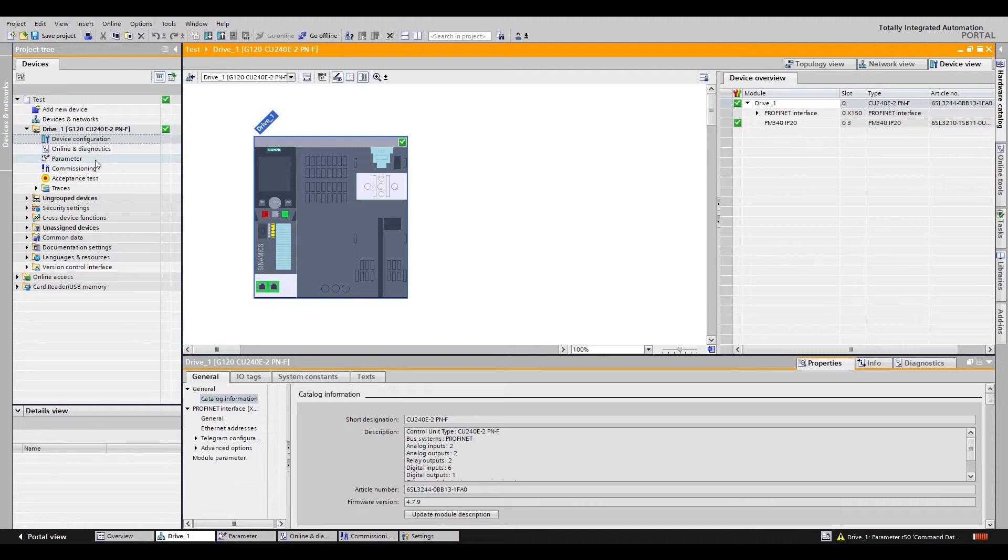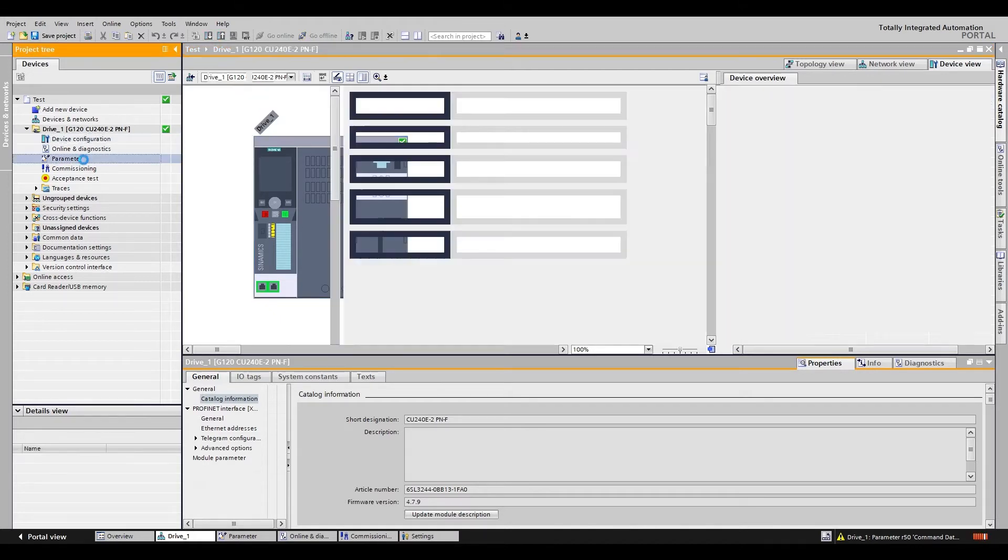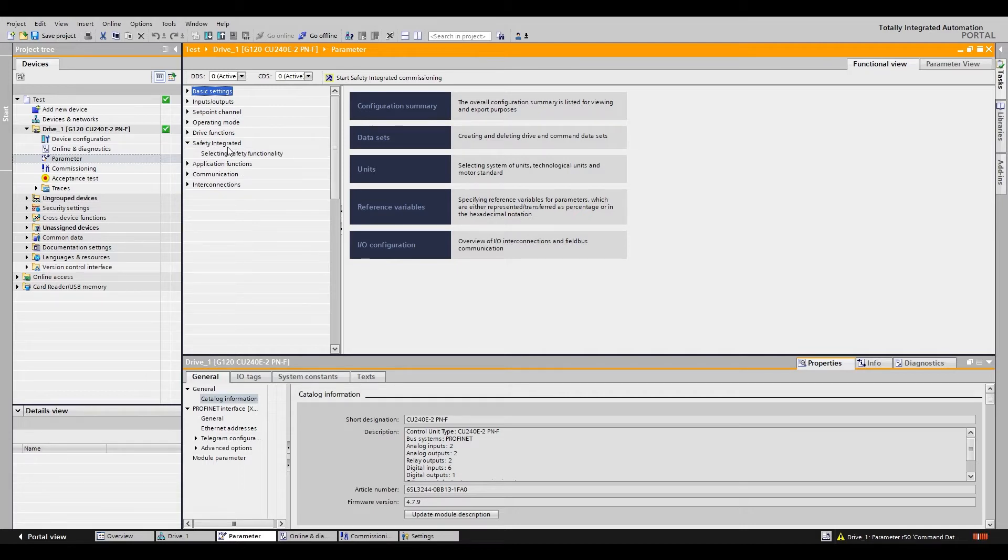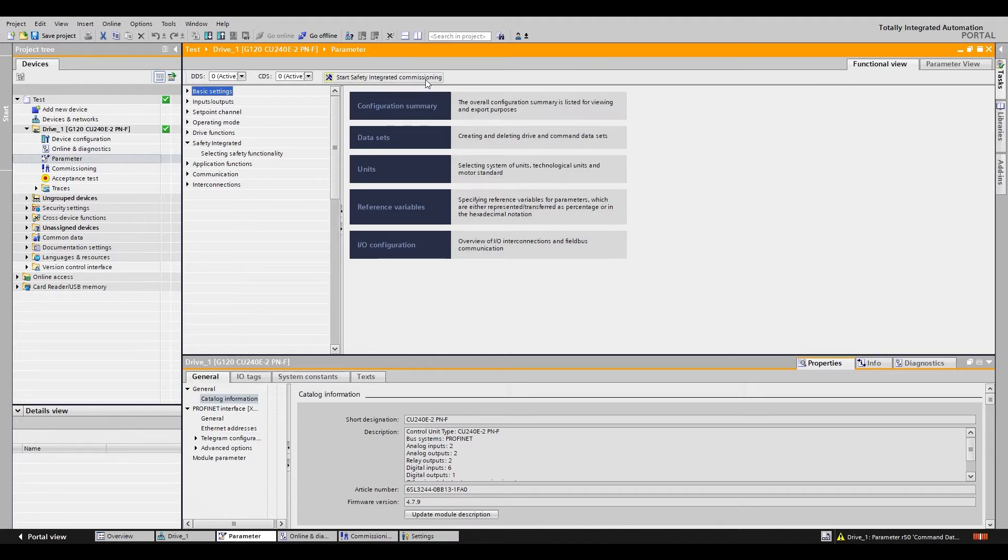To start the process you will want to be online with the drive and go to the parameters of the G120. Then you can select the safety integrated tab and at the top you want to make sure to press the start safety integrated commissioning button. This starts the process that allows you to edit the safety settings.